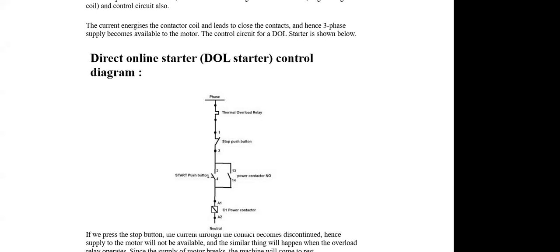If it is a 2-pole motor, it's 3000 RPM. This is a synchronous 3000 RPM, but actual, with the slip frequency, it will run say around 2950, like that. So if it is taking 1 second to reach the synchronous speed, then for 1 second, that 6 times current will sustain. But again, it will be a damped curve.